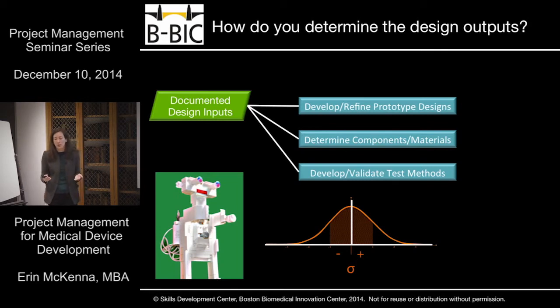So if you're working with materials that have a long history of being used in medical devices, you probably don't need to answer a tremendous number of questions here. So it comes in more when you're using a newer material or a newer formulation. You may want to do some preliminary evaluation to just make sure that you feel comfortable that it would probably pass the tests that you need to from a biocompatibility standpoint.